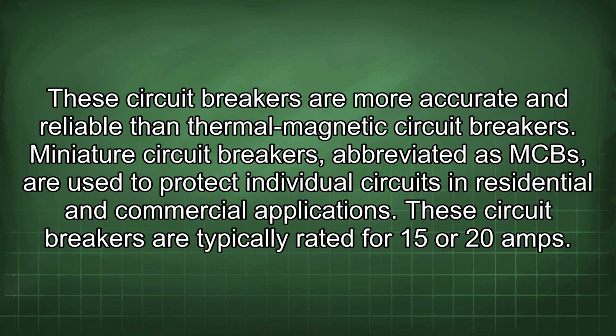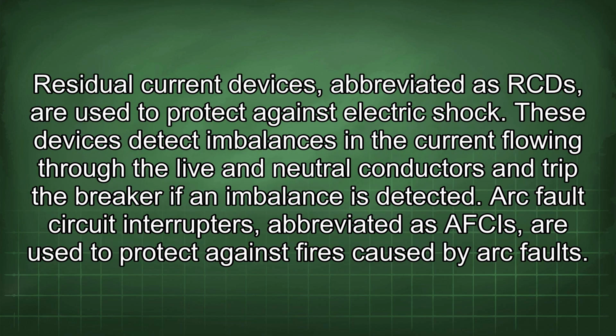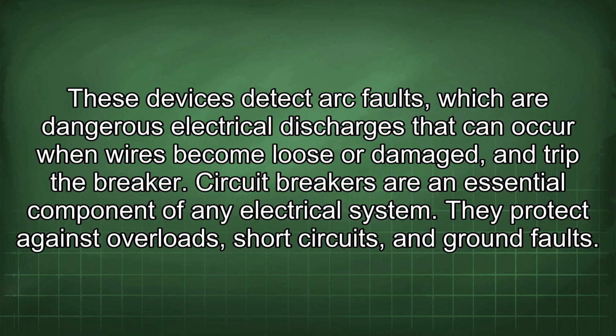Miniature circuit breakers, abbreviated as MCB, are used to protect individual circuits in residential and commercial applications. These circuit breakers are typically rated for 15 or 20 amps. Residual current devices, abbreviated as RCD, are used to protect against electric shock. These devices detect imbalances in the current flowing through the live and neutral conductors and trip the breaker if an imbalance is detected. Arc fault circuit interrupters, abbreviated as AFCIs, are used to protect against fires caused by arc faults. These devices detect arc faults, which are dangerous electrical discharges that can occur when wires become loose or damaged, and trip the breaker.